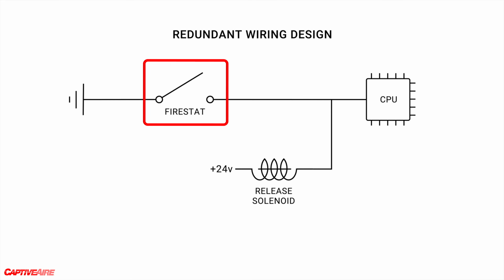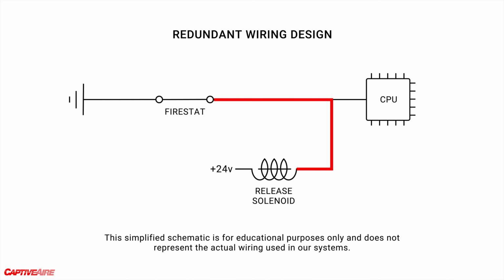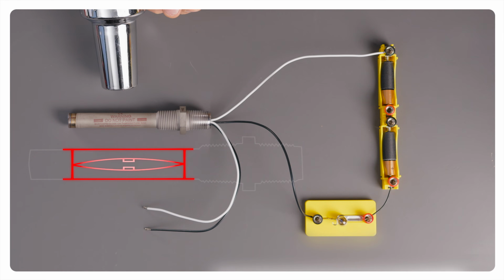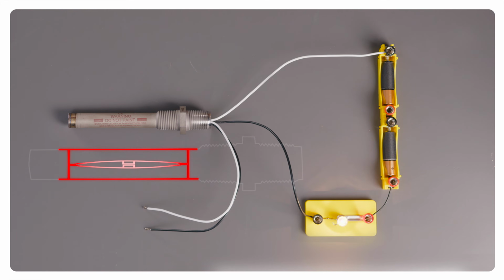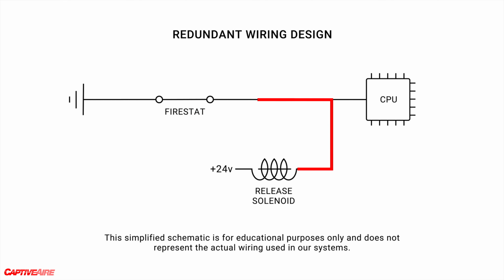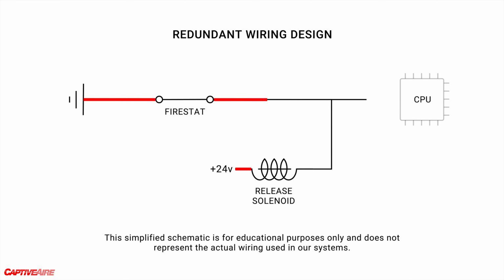Right now, when we detect a fire with the fire stat, it notifies the board, and we loop that signal through directly to the solenoid. The fire stat almost works like a light switch, so a simple contact closure will activate the system regardless of what the board or electronics is doing in the background. In fact, you can actually remove the processor right off our board and the system will still function just correctly. So we don't depend 100% on software for fire activation.